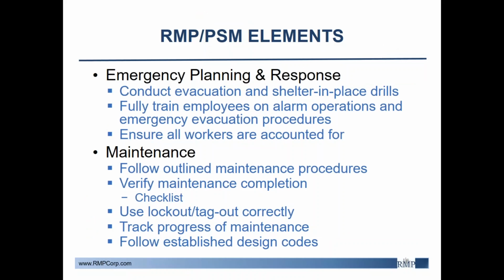So many factors play into the occurrence and severity of this incident. The 2 key prevention program elements to take note of are emergency planning and response and maintenance. First, plant-wide alarm systems were unreliable, and alarm pull boxes were out of reach due to the ammonia release. And also the computerized employee tracking system malfunctioned, delaying supervisors from immediately retrieving a list of personnel in their areas. As a result, handwritten employee and contractor lists were generated based on the workers congregated at safety points. Not all supervisory and security employees were familiar with the employee accountability procedures.